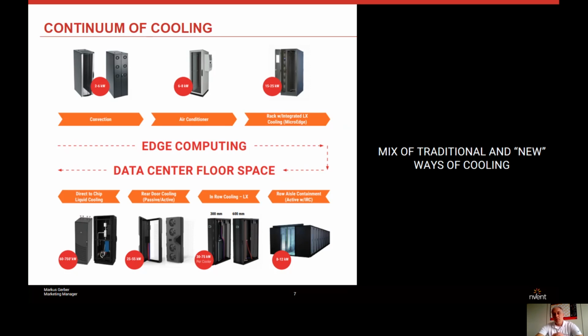And to be efficient, you should consider some active heat exchanger, maybe moving away from refrigerant and DX cooling towards a liquid cooling solution, whether as a side cooler in the rack or as a 19-inch rack mount unit in the cabinet, just to address the needs of these new applications.